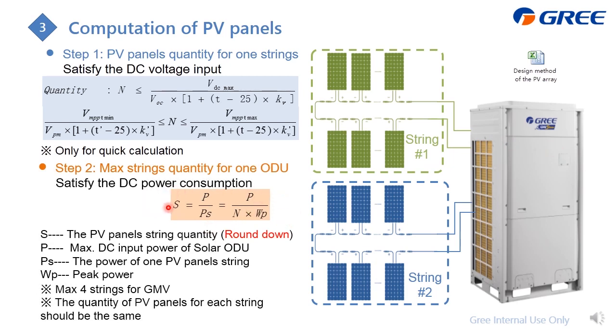You can find this information as well. P is the max DC power of the solar outdoor unit, listed in the service menu. PS relates to that. N is the quantity per string, which you calculated in step 1. WP means the maximum output of the panel. From this, you can finally get the string quantity. The higher this value, the more strings you can connect, which also means you can save more power.